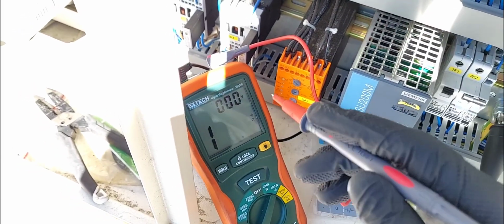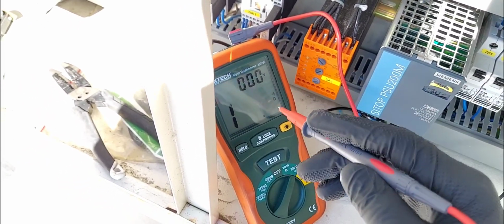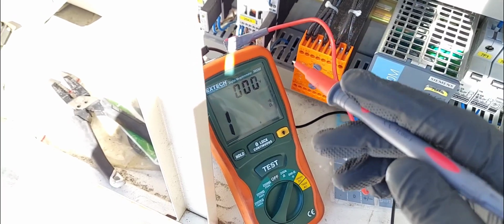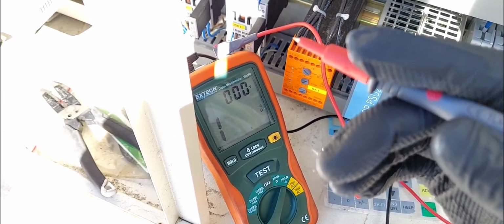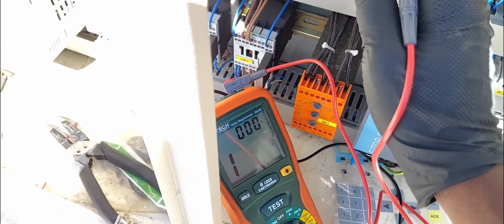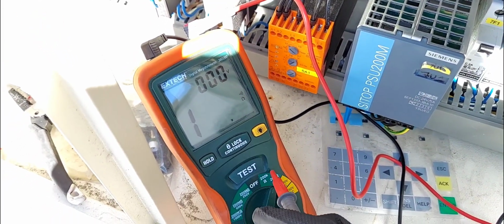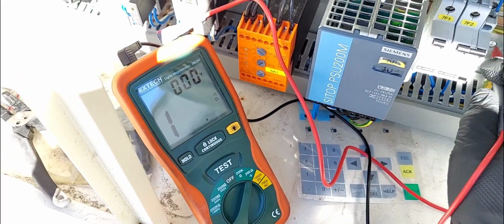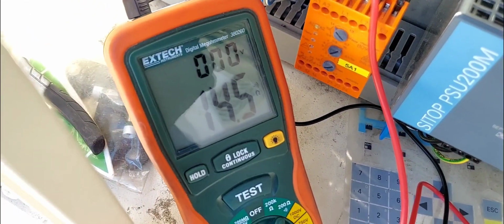But if it's just slightly touching, at times it might pull high amps, it might trip your breaker, it might blow your fuses, and you don't know what's going on. You need to run a Meg test. Because when the winding insulation is getting weak and it's slightly touching ground, it's not fully shorted, so you can't use a regular continuity test for it to ring out like so.